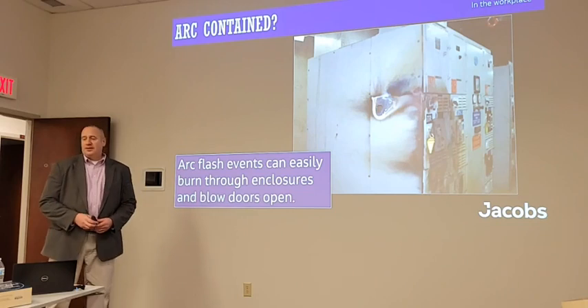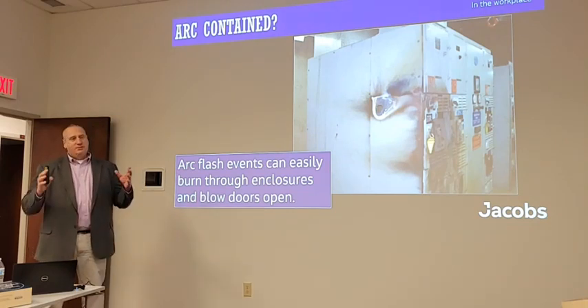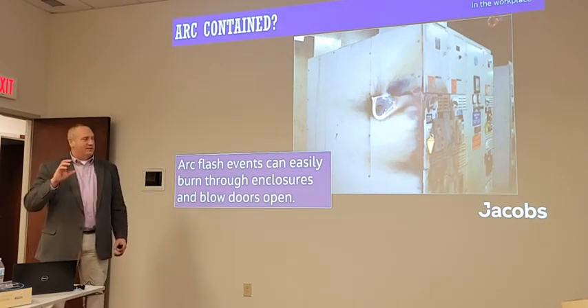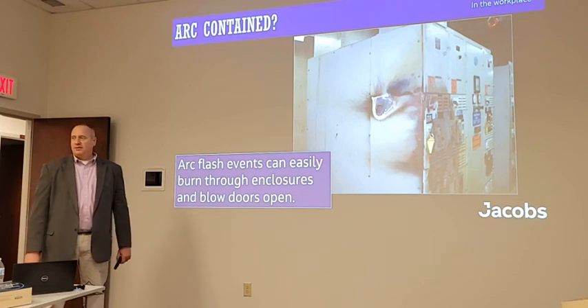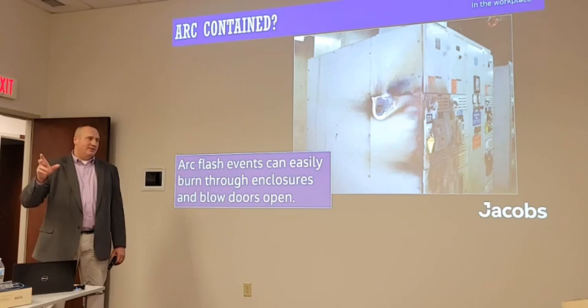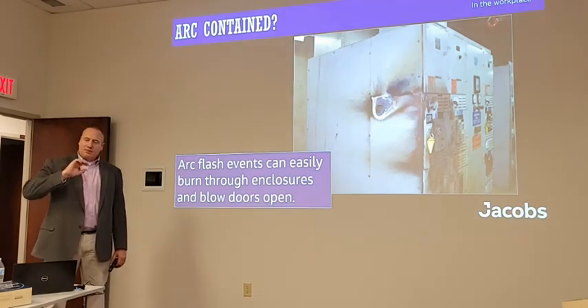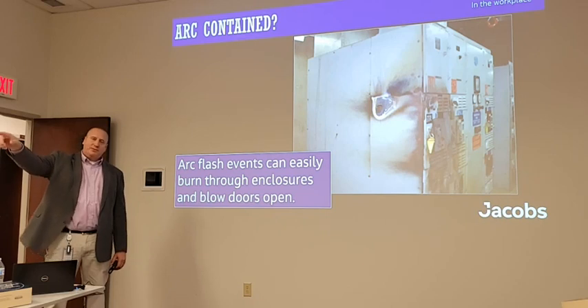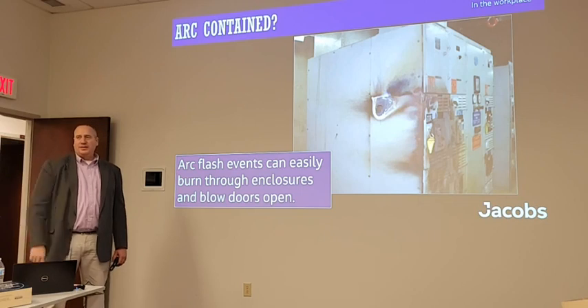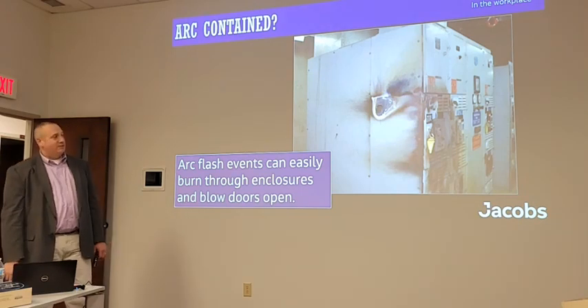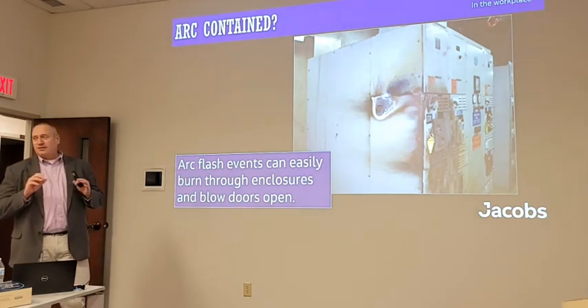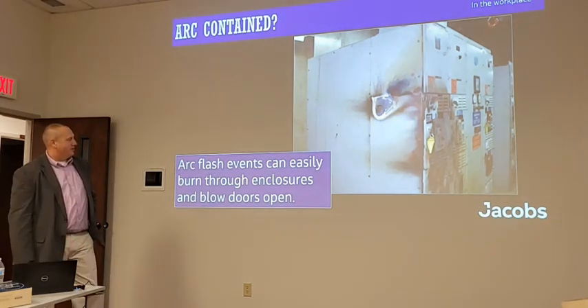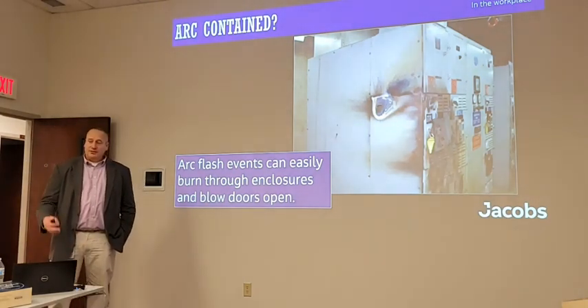I've got a shelf of souvenirs of different bolts and latches and different things that I've collected in investigations of parts that blew a significant distance. In one medium voltage outdoor gear, it blew the panel off about 25 feet, and we're picking up strip bolts like 50 to 75 feet back behind it. And so it's a lot of energy trying to escape instantly. You can't count on the doors being closed to protect you unless it's arc-rated gear.